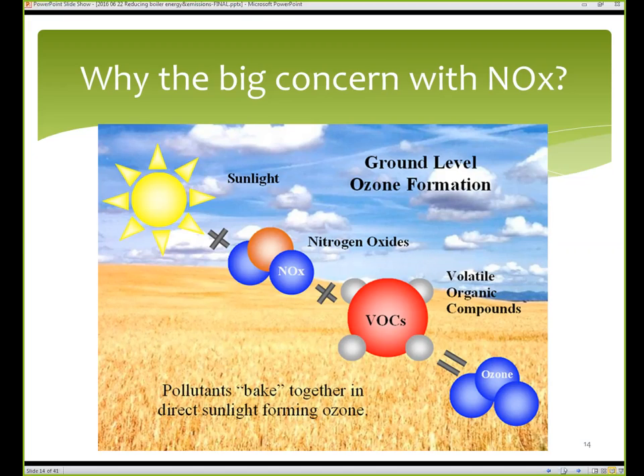So in areas of the United States that are out of attainment for ozone, or non-attainment, some boilers are required to limit their NOx emissions, sometimes through controls like low NOx burners. Wichita and Kansas City areas are closely monitoring for ozone. The ozone standards got more strict at the end of last year, and there's a good chance these two cities could become non-attainment for ozone. So KDHE and local air quality groups are focused on outreach and education to reduce NOx and VOCs, and today our focus is on the NOx.